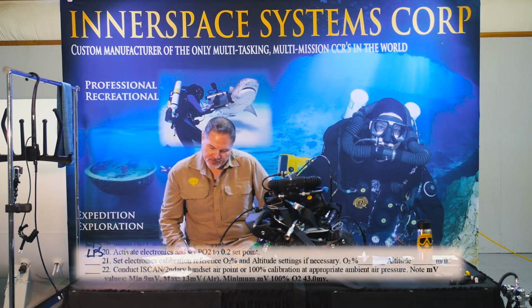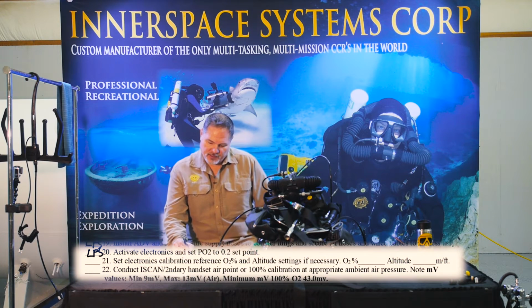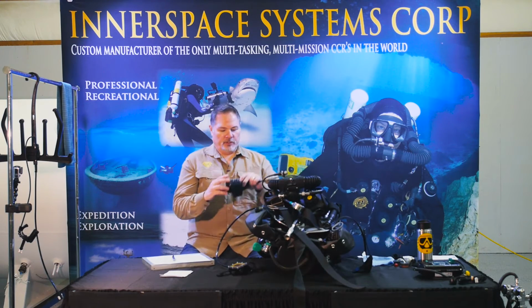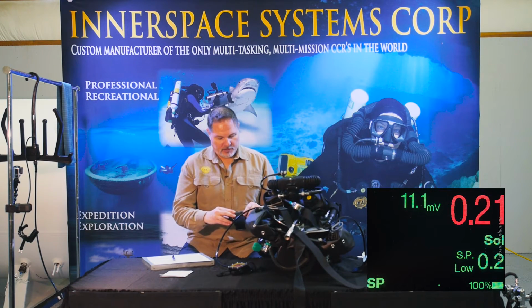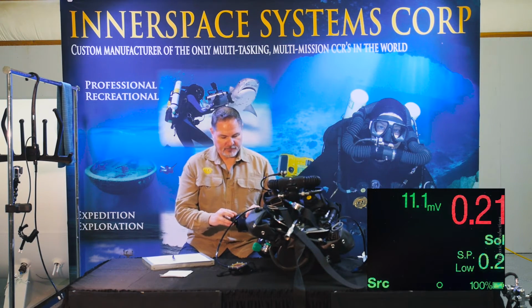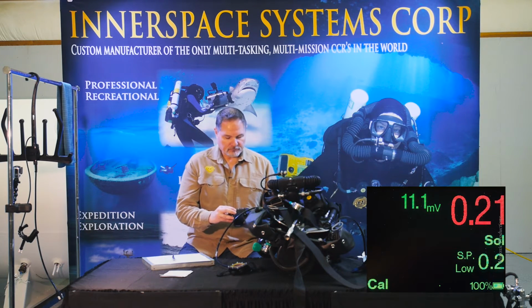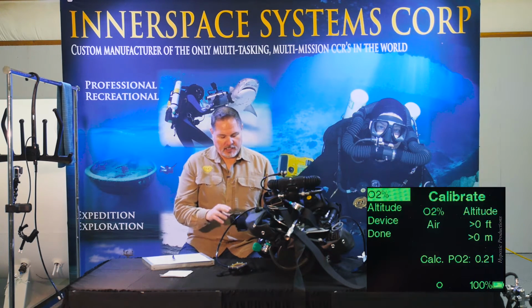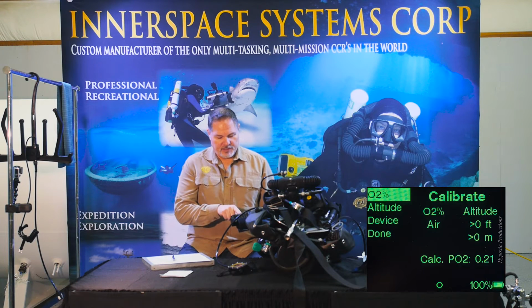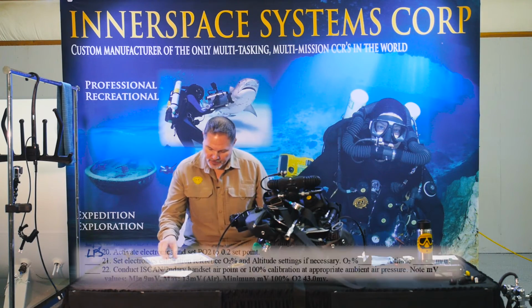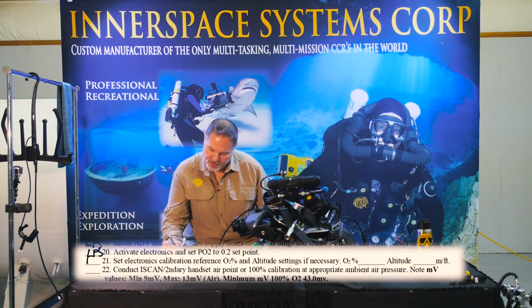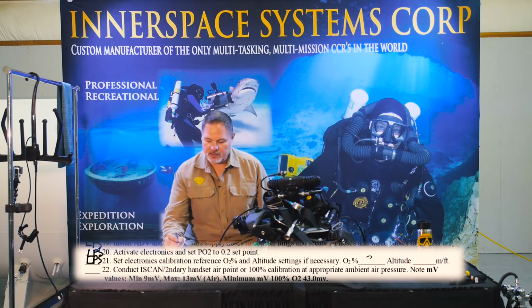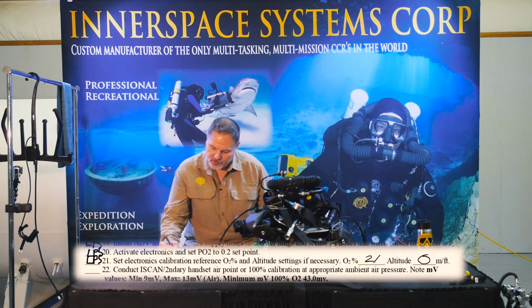Set electronics calibration reference, oxygen percent, and altitude settings if necessary. So I'm going to go through here to calibrate mode, and you'll see this later on another video. I'm looking down in calibrate mode. It says my air reference for calibration is air, and my altitude is at 0 feet. I'm good to go there. All right, so I'm going to put 21%, my reference gas for calibrating, and my altitude is 0 feet or meters.